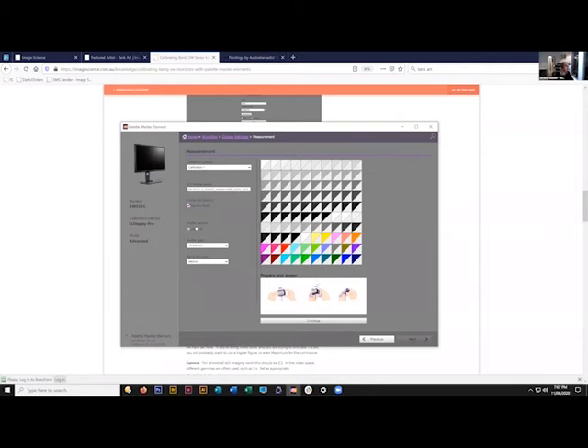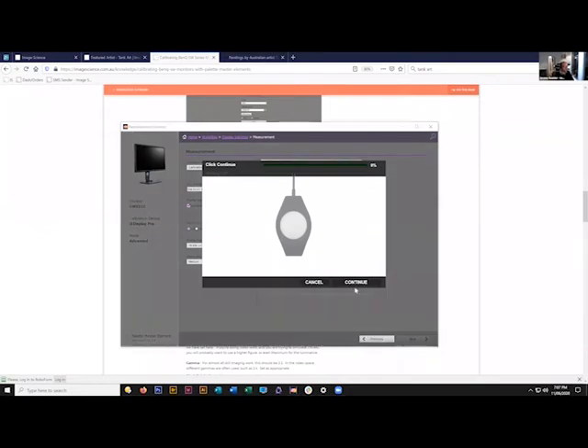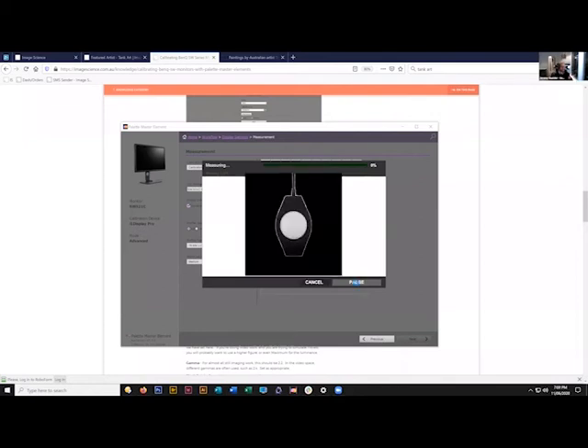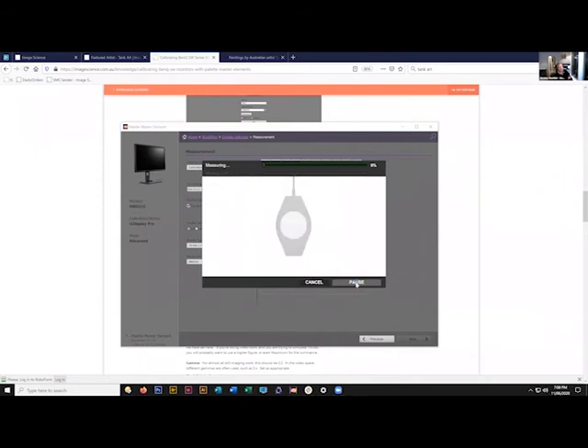The other question, do you need separate calibrations for day and night, is an interesting question. I'll just get this process started while we talk. It's asking me to place it in the right spot, and now I'll hit continue. Whether you need separate calibrations really depends on how much the light varies in your working environment during night and day. In reality, if your light varies so dramatically that you do need a separate calibration for night and day, then probably what you should look at, rather than having multiple calibrations, is controlling the light in your work environment.